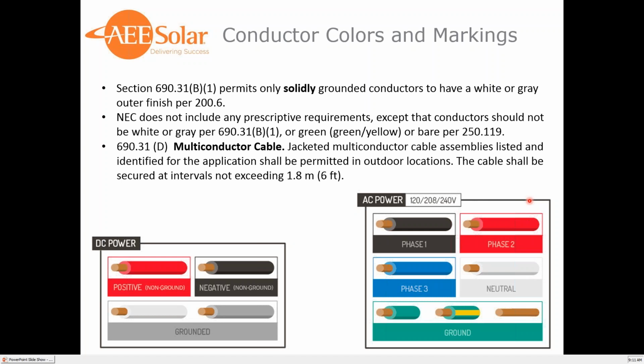So essentially, common practice has been to use red for the positive, black for the negative. You have to be careful when you're doing this. Red can actually fade to a whitish looking color, which could cause issues later. A lot of times people will just use two black wires and just tape red tape, so many feet on the conductor to identify it.